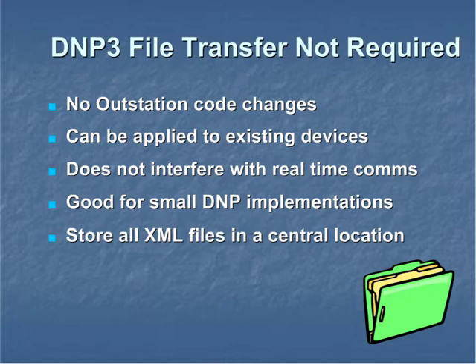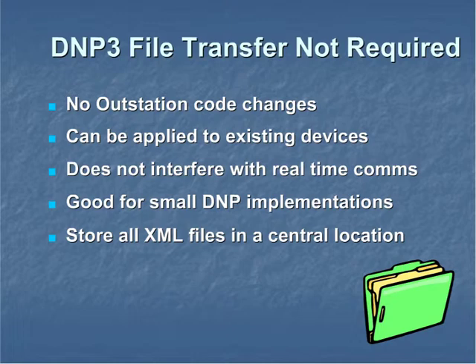Note that no outstation code changes are required to support the new DNP3 device profile in XML. The XML file is just a new file that's supplied on disk or by a web download. This format file can be applied to existing devices that were placed in operation years ago. It does not interfere with real-time communications and is good for small DNP implementations as well.